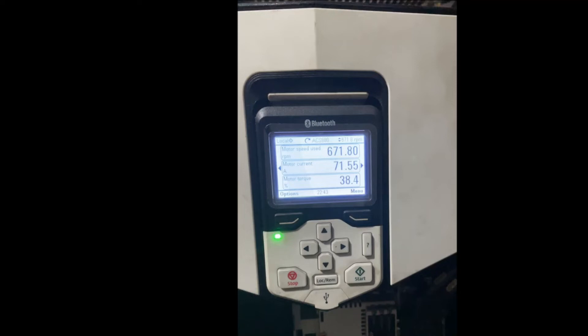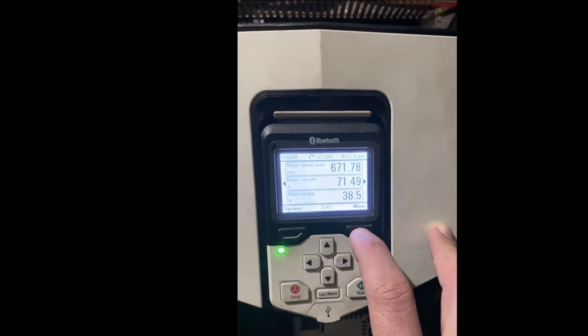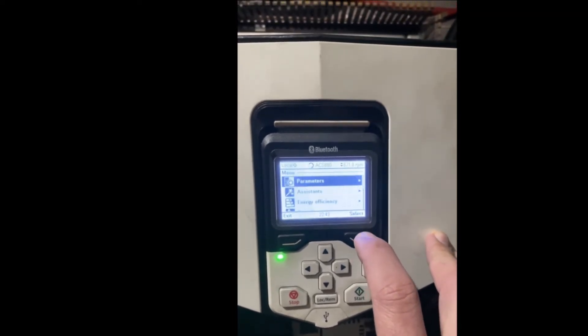Hello, here I have an ABB drive which is the ACS 880 with ACS-AP programmable panel, and we're going to show how to copy the parameters from the drive to this panel — to have a copy stored or to change the drives. The steps to do that start with pressing Menu.